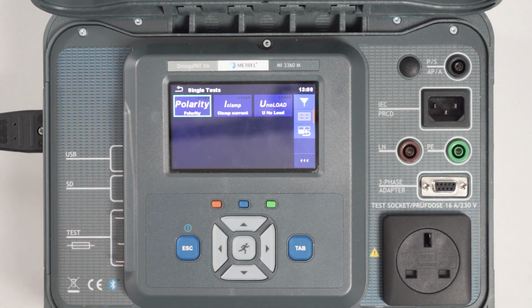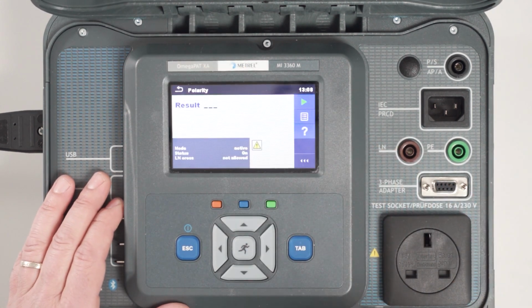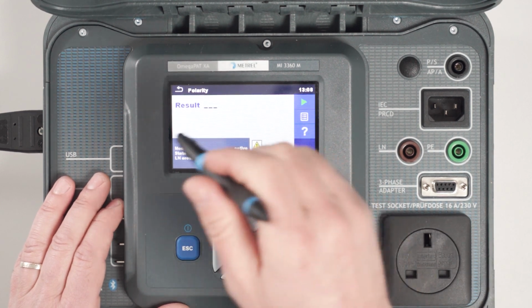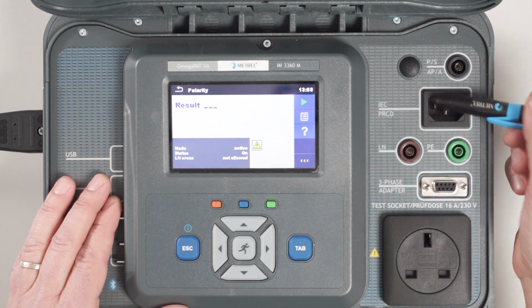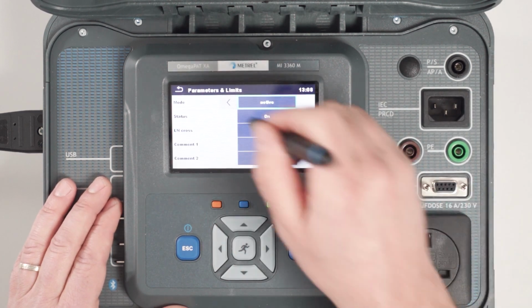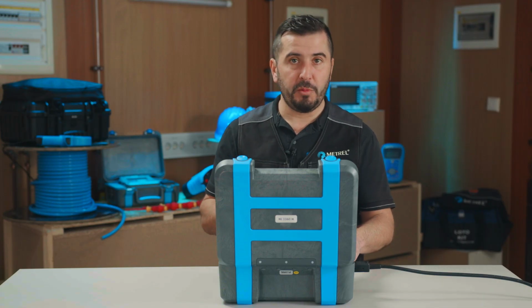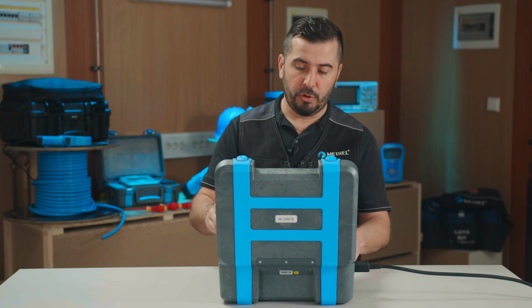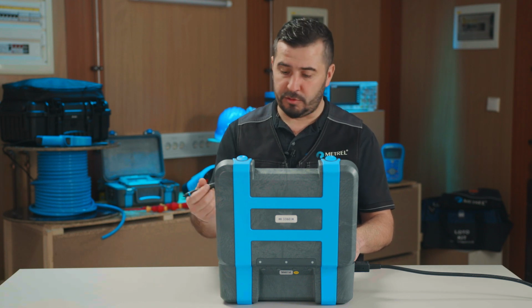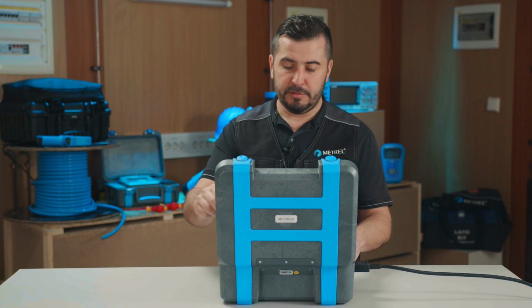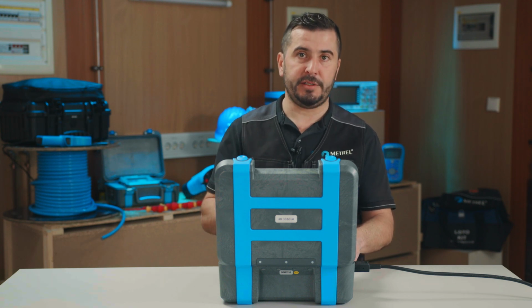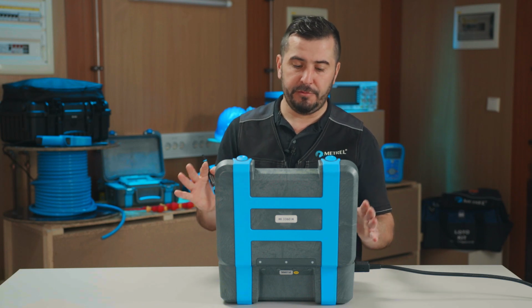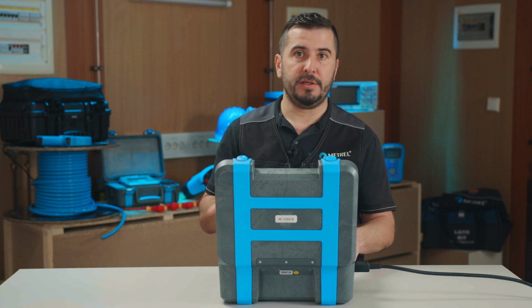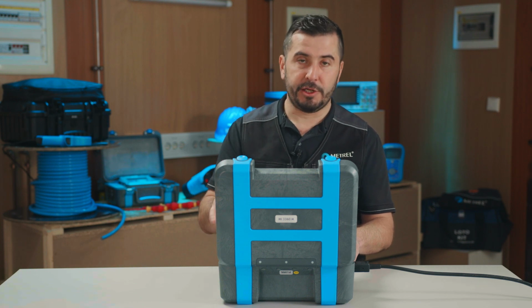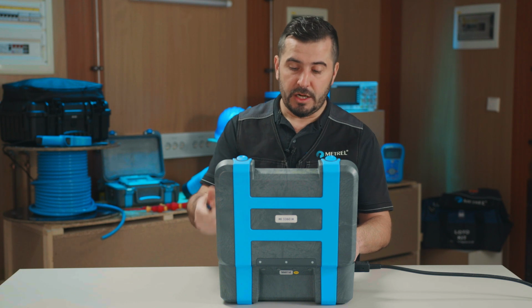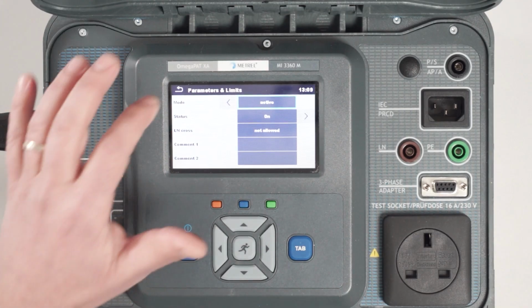Inside here we have the option to test polarity of our IEC cords or extension leads. Again, one very nice feature of this polarity test is that we can perform polarity between these two terminals in normal mode, meaning that the instrument will generate voltage and current for the test signal itself, or we can use active polarity test. This is important when we are measuring polarity on extension cables equipped with portable RCDs, because we have to arm the RCD to check the polarity itself.